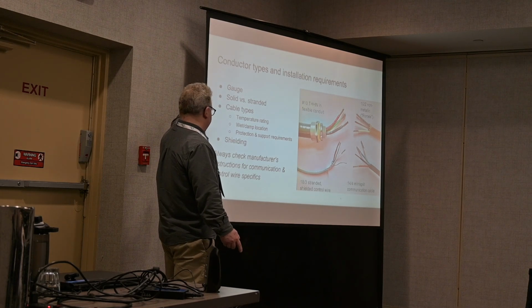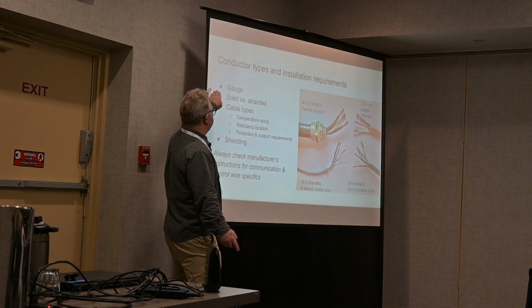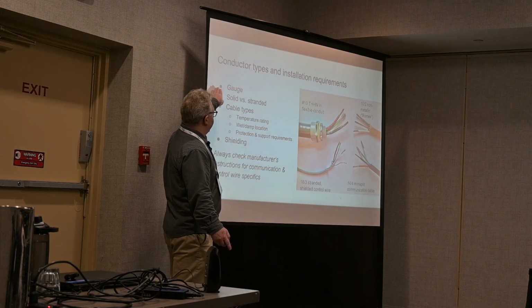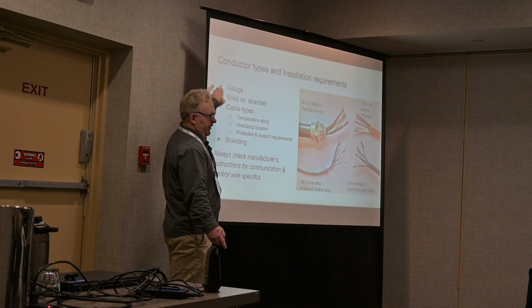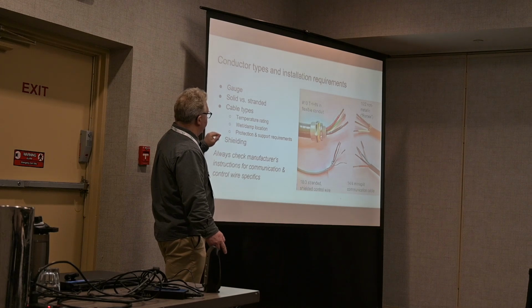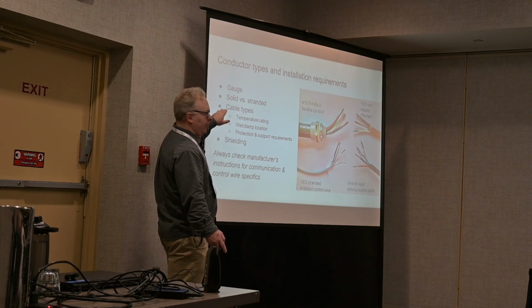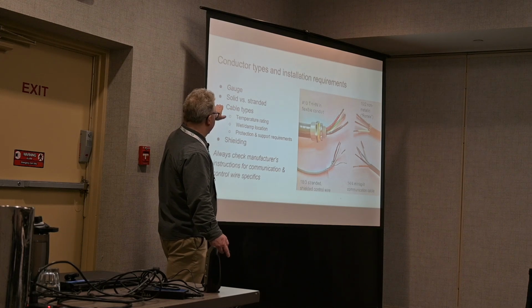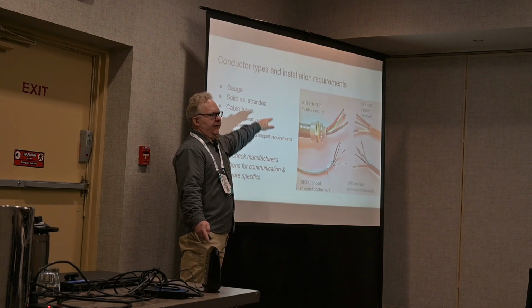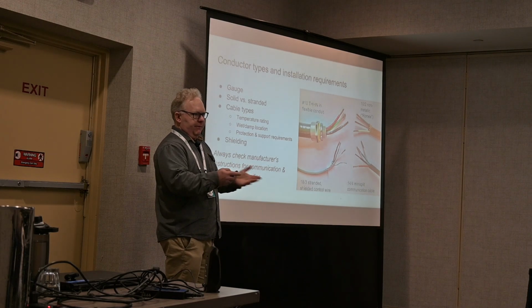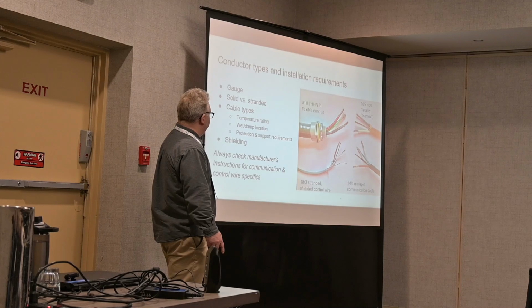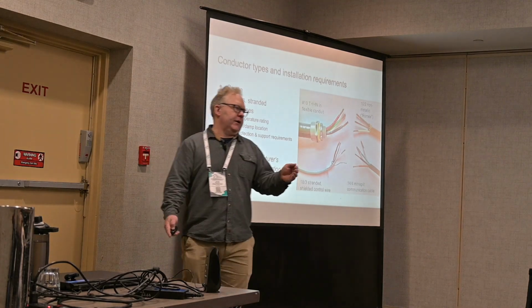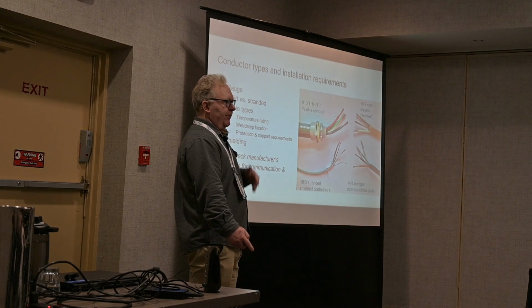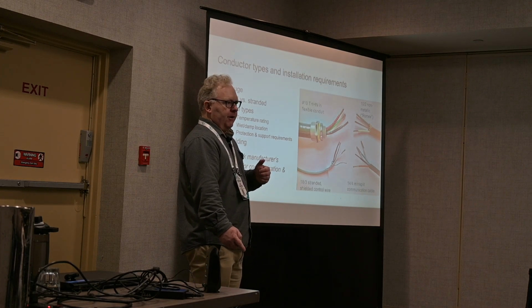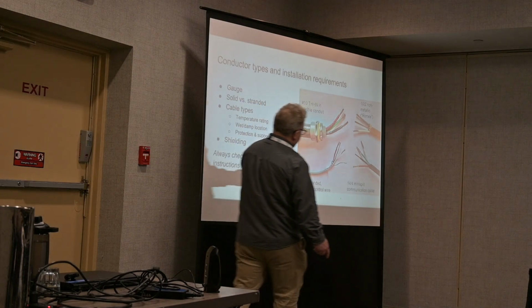A couple things to keep in mind. One is that wire gauge and ampacity are absolutely critical in delivering power to these. When we look at control applications and communication applications, a lot of manufacturers are going to want to see stranded wires because they're better at transmitting the communication signals compared to solid wires. And they'll often specify a specific wire type and gauge. For example, the mini splits I'm familiar with, it needs to be 14-4 mini split communication wire, and it needs to be stranded, not solid.